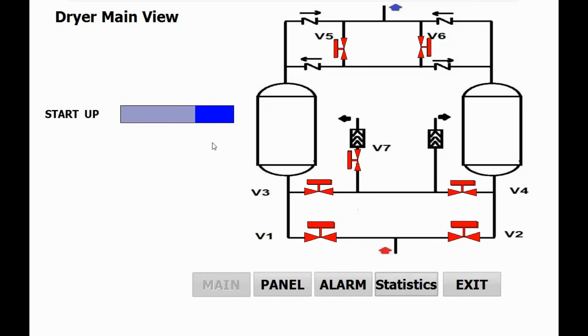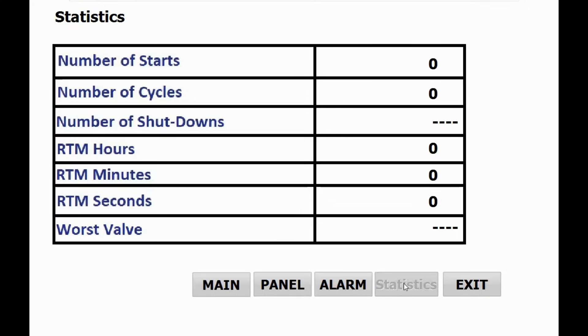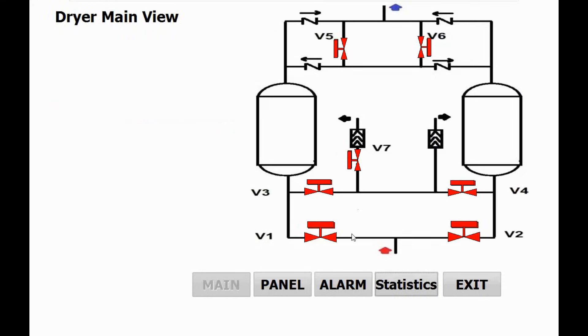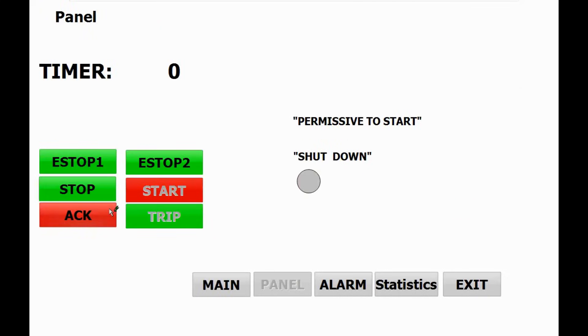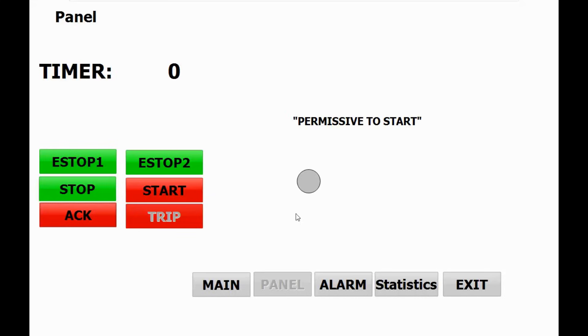After the startup time is finished, we have the chance to start the dryer. That will be part of the course: how the dryer is programmed, how actions are issued based on the sequence, and how feedback regarding the open or close status of each valve is monitored. We define a statistic form for the machine and will report number of starts, number of cycles, runtime in hours, minutes, and seconds. If some valve has a mechanical problem, we gather that failure information and report which valve has the worst record. Once we acknowledge the alarm and shutdown, we have the permits to start and can run the machine.